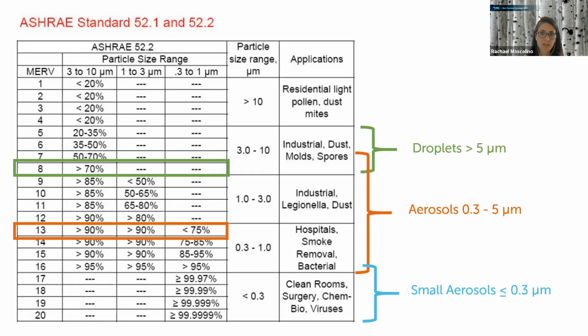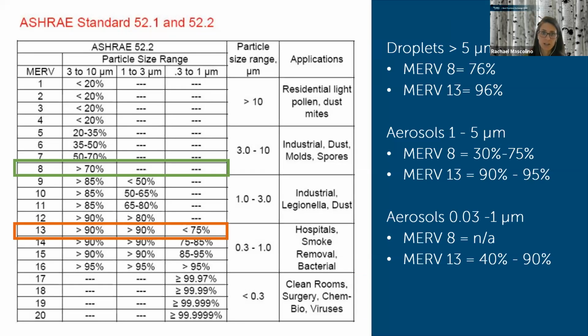You see the droplets are 5 microns or larger, and then aerosols are 0.3 to 5, and then there's some talk of those smaller aerosols. But it's pretty clear to see that's where that 0.3 to 1 micron range starts to become effective and kick in right at MERV 13. And so that's why MERV 13 is the target. Another way to think about it is to compare the effectiveness by particle size. So again, the priority is filtering the air that's being recirculated in one HVAC zone.